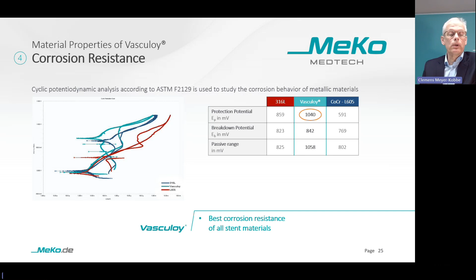The value for the protection potential reflects the healing effect of the surface if the surface of the stent is scratched, for example, by a guide wire, or if two stents are in contact in a bifurcation vessel situation. With a high protection potential, the stent surface heals faster and regains corrosion resistance. And you can see that Vasculoy has by far the highest protection potential of here more than 1000 millivolt, higher than stainless steel, and far better than L605. So the take-home message is Vasculoy has the best corrosion resistance of all stent materials.